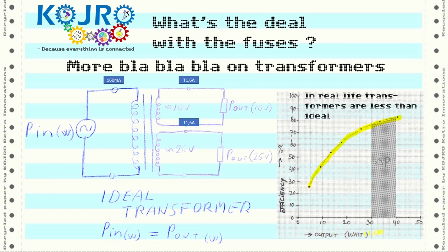But this is the stated efficiency of a normal iron core transformer, and the more you draw from the transformer, the more efficient it gets. This is different for every transformer, and a bigger transformer tends to be more efficient than a small one. But just to give you a rough idea, they state our transformer should have an efficiency in the range of 80 to 85%.